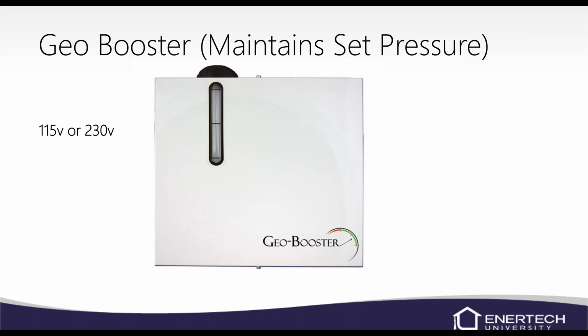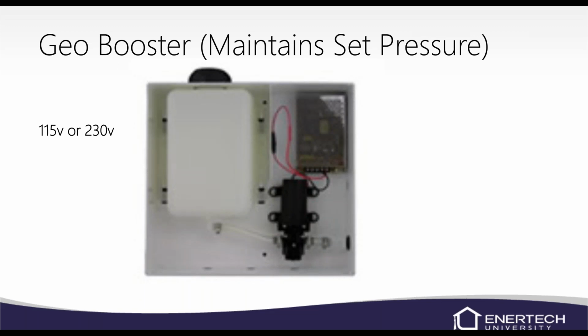But if it takes 6 months to drop pressure or something, you can get what we call a Geo Booster, and it will maintain a set pressure of anywhere from 25 to 35 PSI. Basically, there's a little black pump inside here in the lower right corner, and it's got a tube that will run directly into your source piping, or you can tie it into the PT port with a needle and a T, so you can still check your pressure drop. It looks at pressure back to the pump, and once it drops below that pressure, it'll turn that pump on and drop some of the fluid in the reservoir into the system.